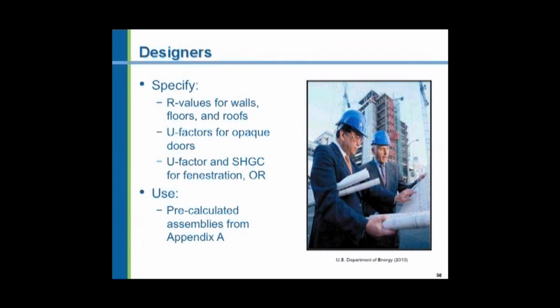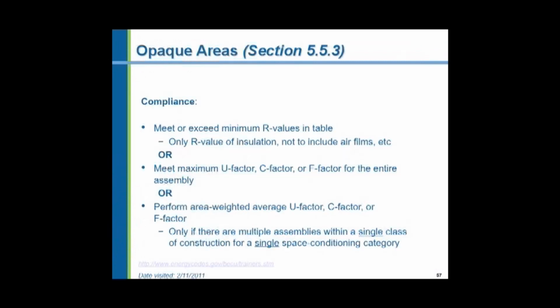The builder has to know that that data has to go to the plan reviewer. So he either submits the book of specifications or he has the architect put all that stuff on the drawings. The tables that we talked about mention the R value of insulation. That is only the insulation component of the building envelope. It does not include the studs, the framing, the sheathing, the siding, anything at all, the air surfaces. It's only the insulation component that we're talking about.